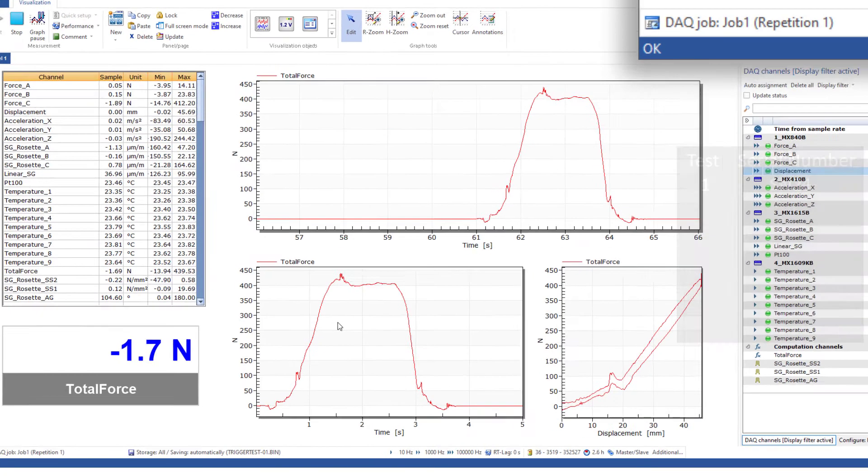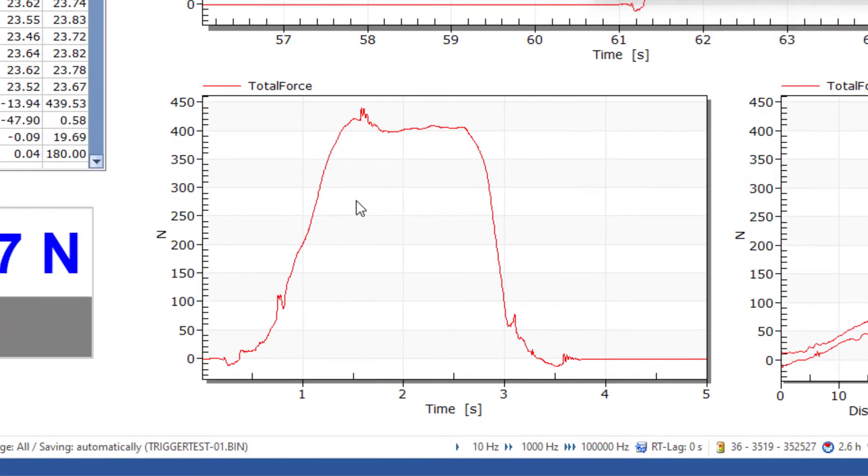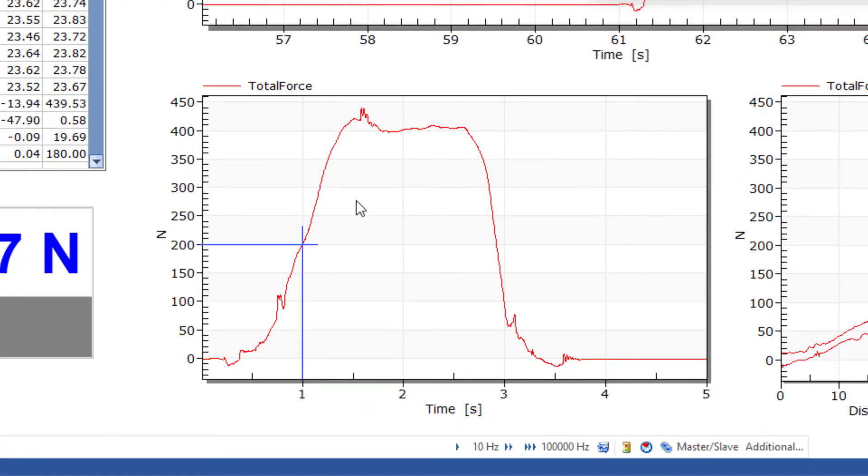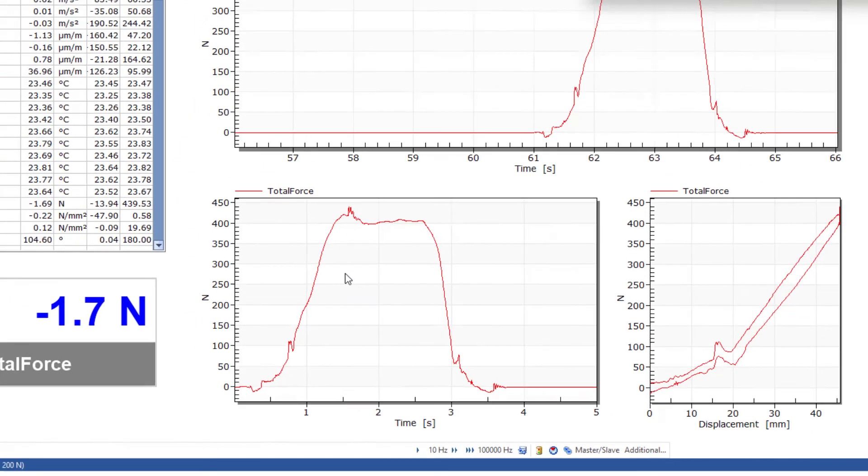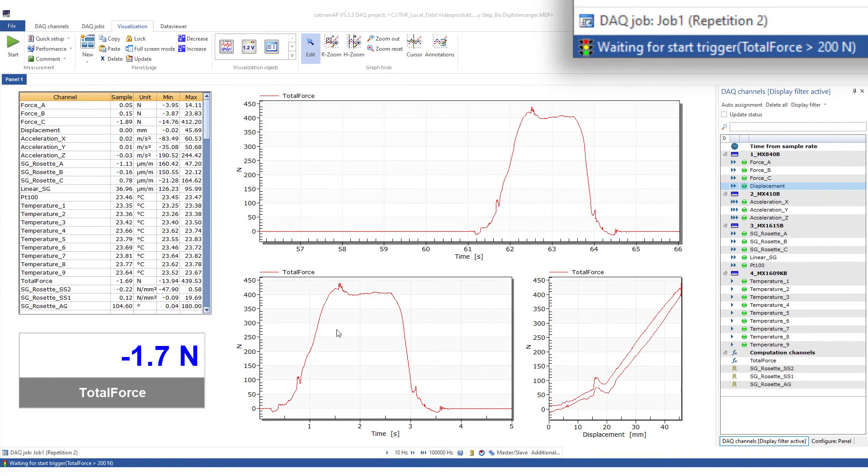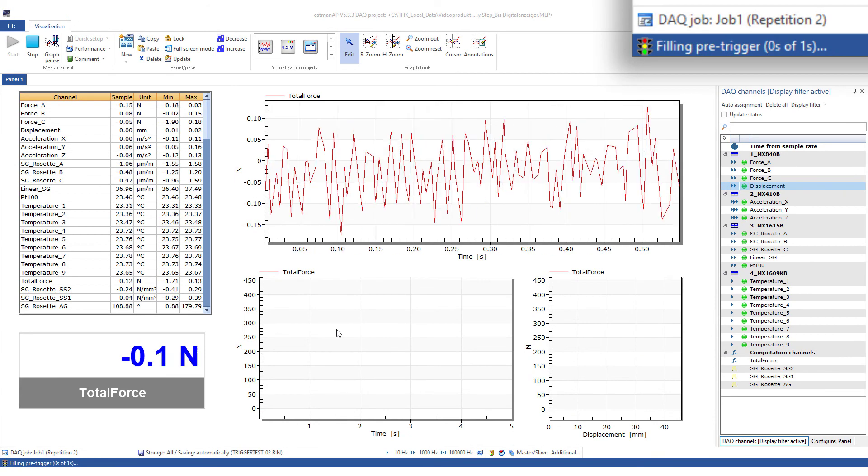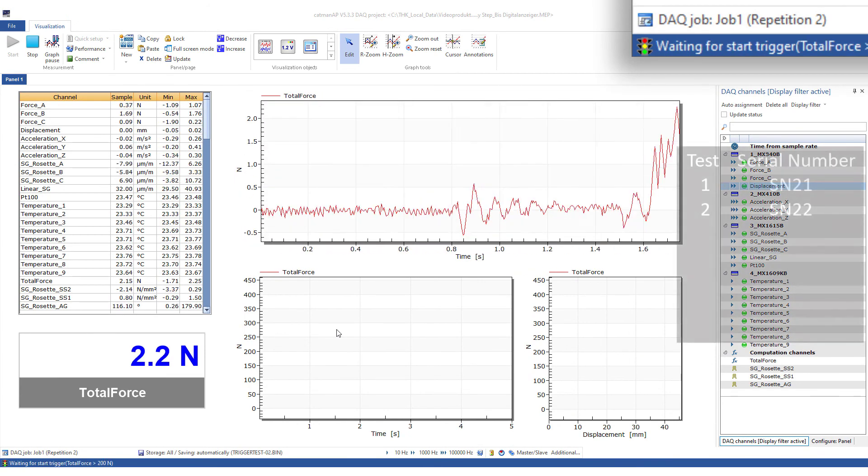Here, I stop the video recording briefly and show the trigger time. The graph shows that the curve reaches 200 newton after one second. Every further measurement we take will pass through this point. Therefore, the selection of the trigger threshold is essential if you want to display the curves of several measurements in one graph for comparison.